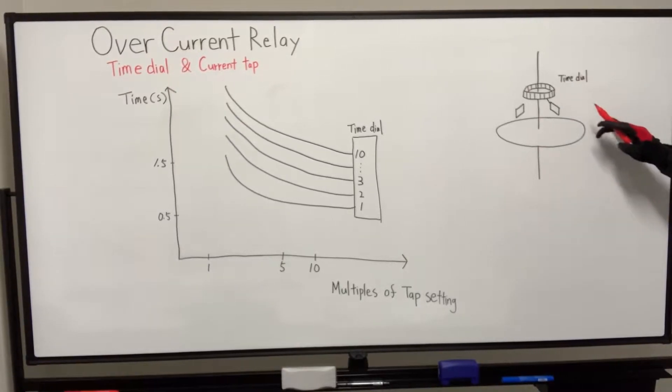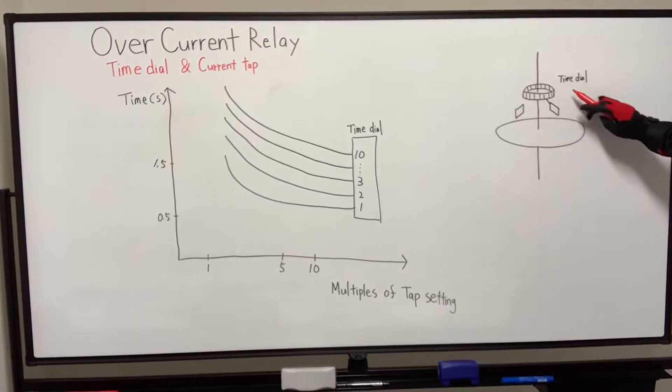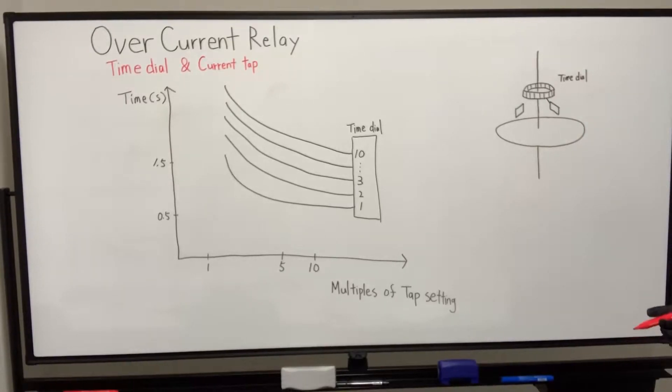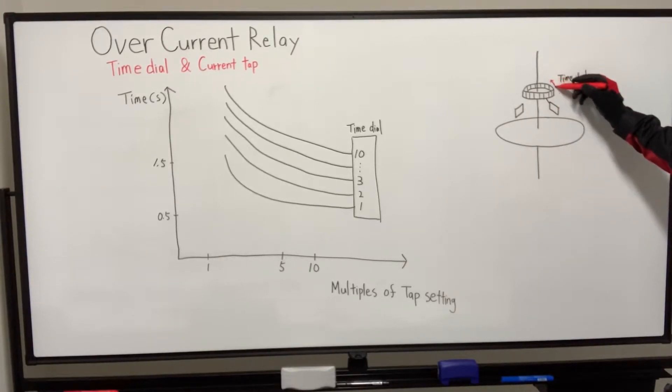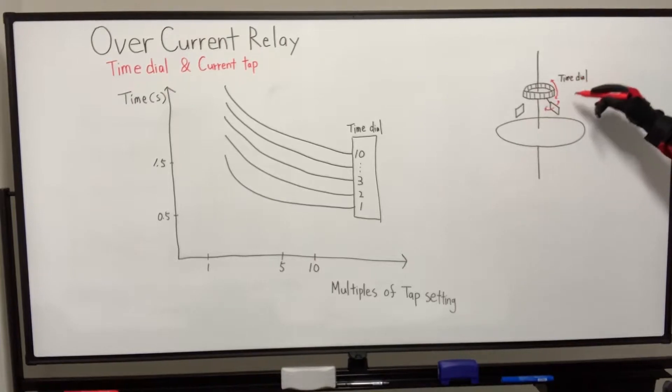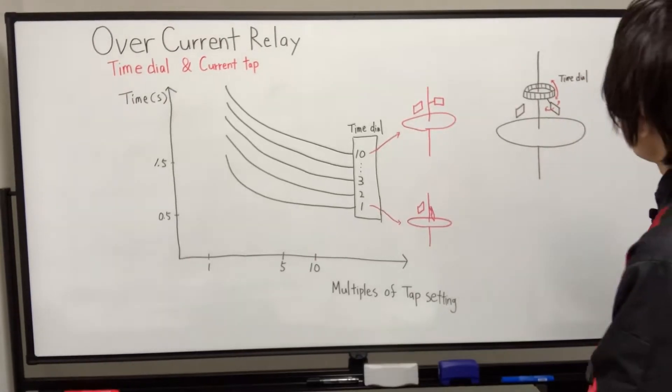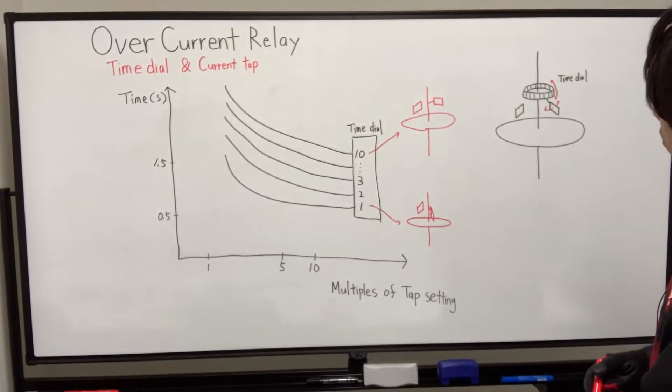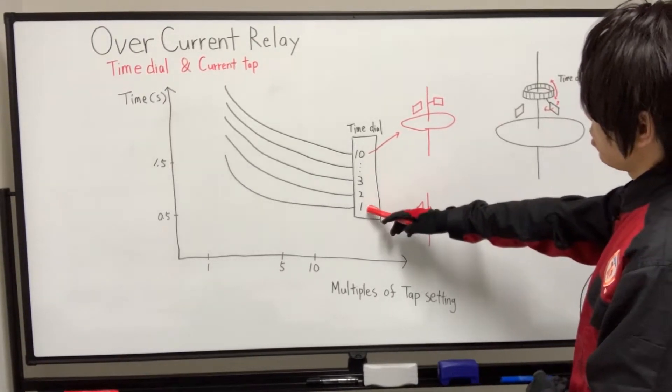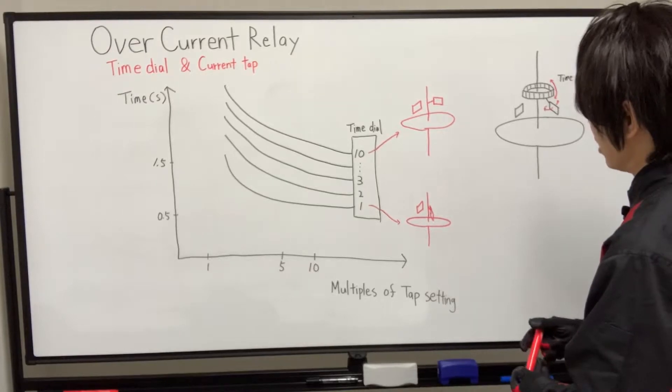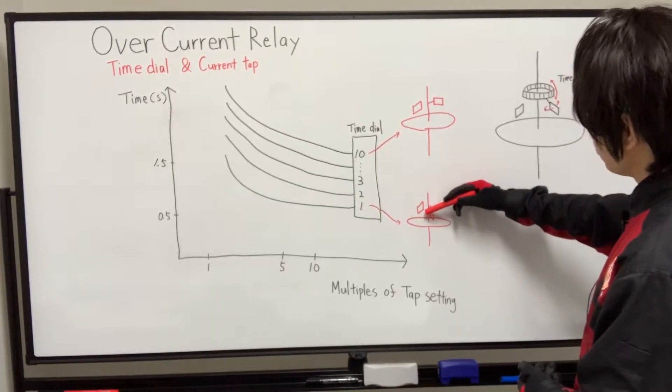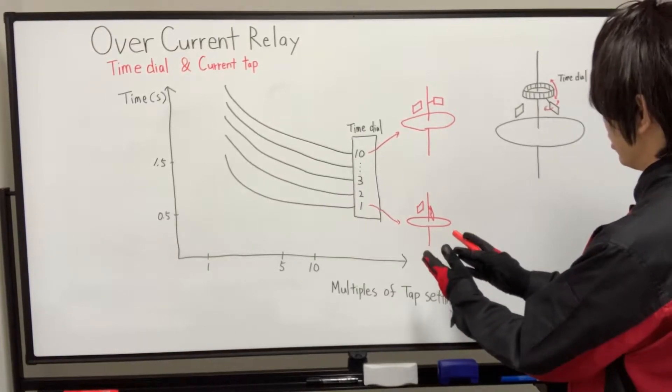This diagram represents the construction of the relay, and here is the time dial. What this actually does is change the distance between fixed and moving contact. So with the dial, we can adjust the distance here to the moving contact. As shown in this family of curves, if the time dial is set to number 1, it indicates the shortest operating time - the fixed and moving contact distance is very close.